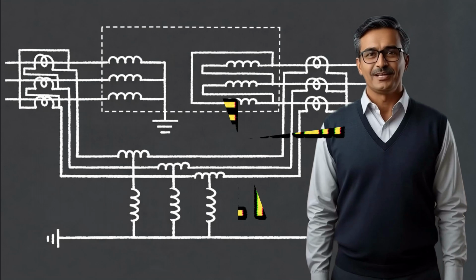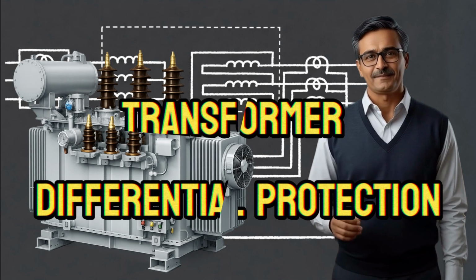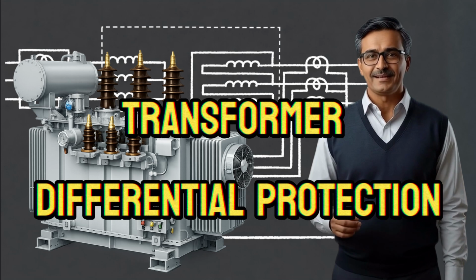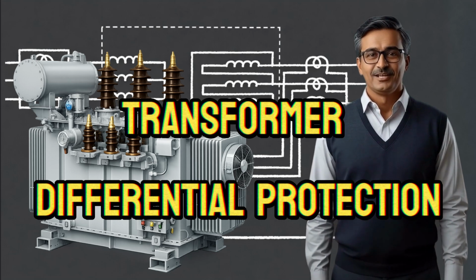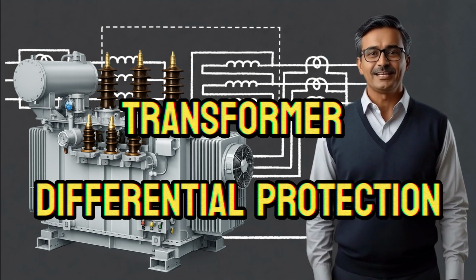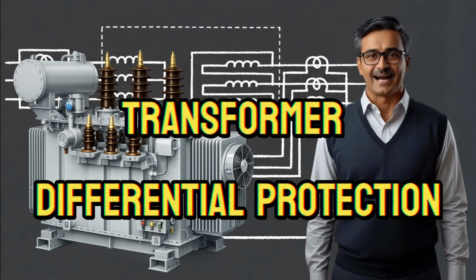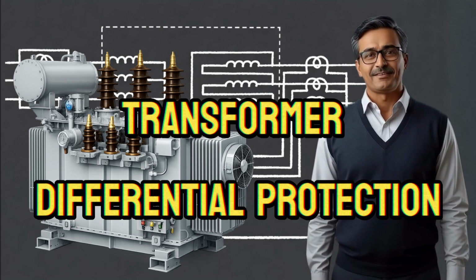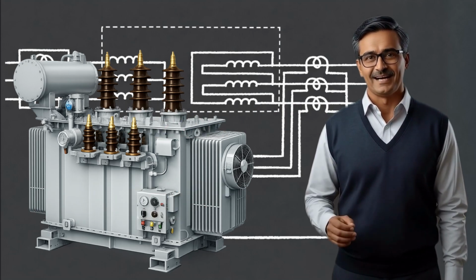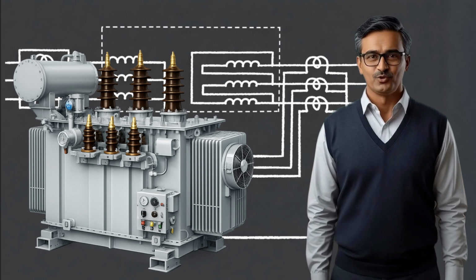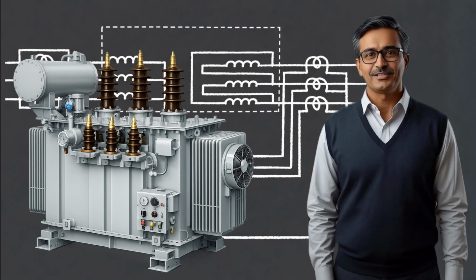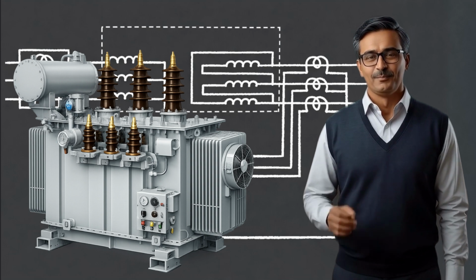In this video, we discuss transformer differential protection, a special protection scheme that detects only internal electrical faults. The relay continuously compares the current entering and leaving the transformer. If this current balance is disturbed, the differential relay operates and isolates the transformer from both the high voltage and low voltage sides. For external faults, the differential relay does not operate.